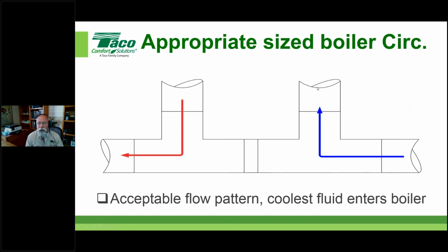The other thing is people say, well, I've got two pumps on there, what if I just make the pumps the same size? Won't I get this as an end result? And I'll say, well, it's really hard to do. It's acceptable, but just not very practical. The idea of putting two pumps that are equal size and expecting equal flow goes against everything we teach about pressure drop calculations and understanding how something within the fluid flow impacts the pressure drop. It's really hard to do without balancing valves and all this other nonsense. So just understand that.